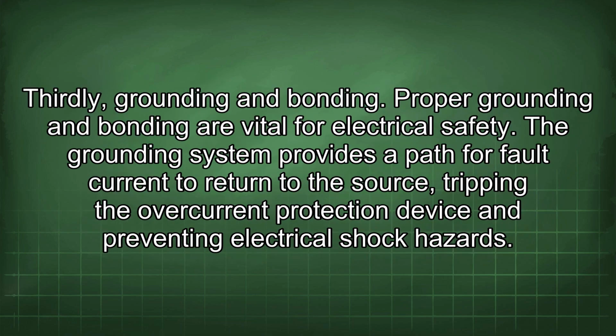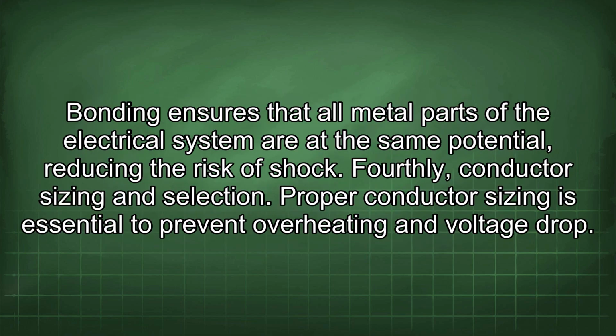Thirdly, grounding and bonding. Proper grounding and bonding are vital for electrical safety. The grounding system provides a path for fault current to return to the source, tripping the overcurrent protection device and preventing electrical shock hazards. Bonding ensures that all metal parts of the electrical system are at the same potential, reducing the risk of shock. Fourthly, conductor sizing and selection.